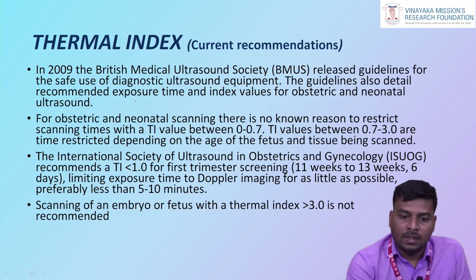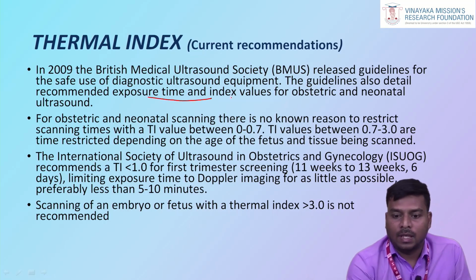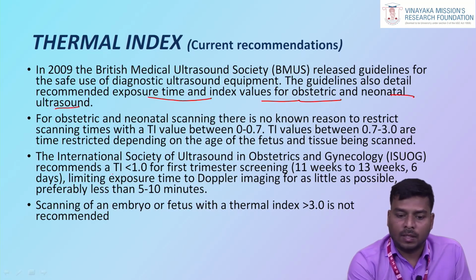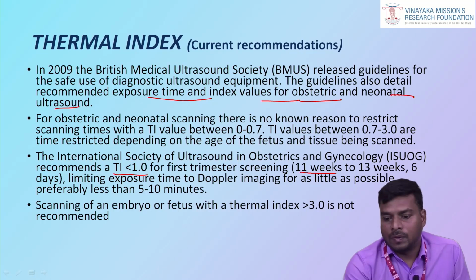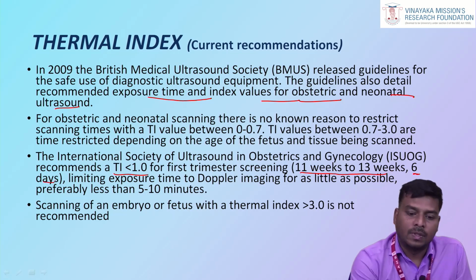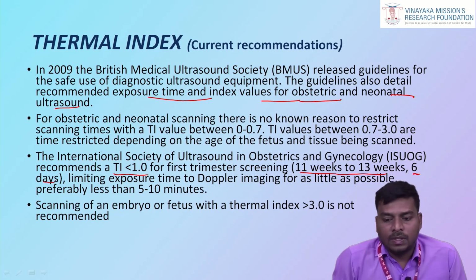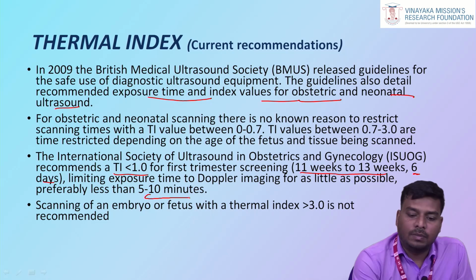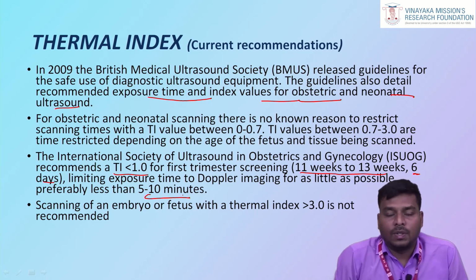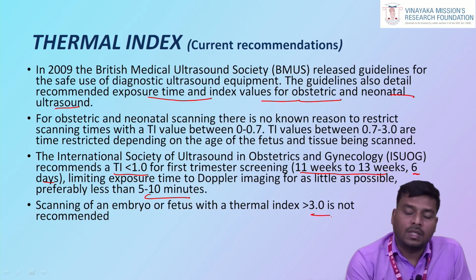Before that we discussed the recommended exposure time and index values for obstetric and neonatal ultrasound. The International Society of Ultrasound in Obstetrics and Gynecology recommended a TI value less than 1.0 at 11 weeks to 13 weeks, 6 days. Limited exposure to Doppler imaging, preferably 5 to 10 minutes. Scanning of the embryo or fetus with a thermal index greater than 3.0 is not recommended.